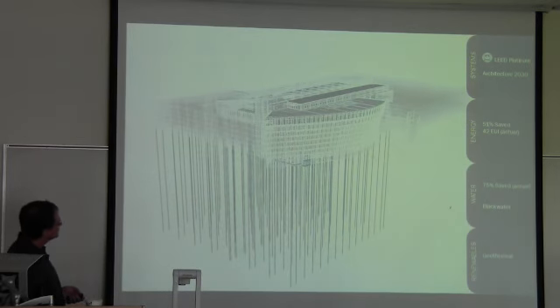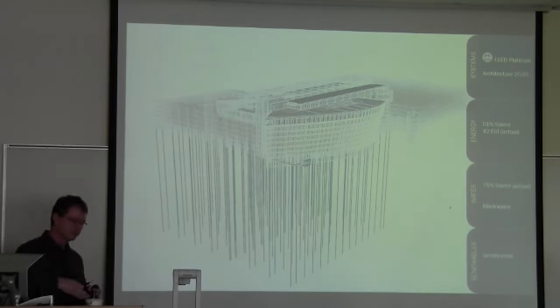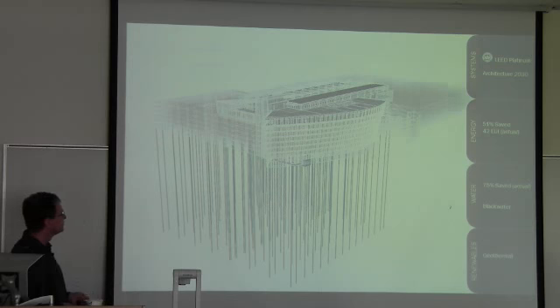This is a graphic that shows those wells that are under the building. It kind of gives you an idea of the scale and the reach of what that heat exchanger is doing under the space. It's a high-density polyethylene piping. That's the same piping that Northwest Natural uses for running high-pressure gas lines through the city of Portland. It's very resilient. You can freeze it up solid. You can move it, deform it. It's a very good material for use in underground, because once this goes in, the procedure is that you drill like a water well. You drill a well with an auger bit. You pull the auger bit out, and you have this 5-inch diameter hole that's 340 feet deep, and then you bring the piping material.